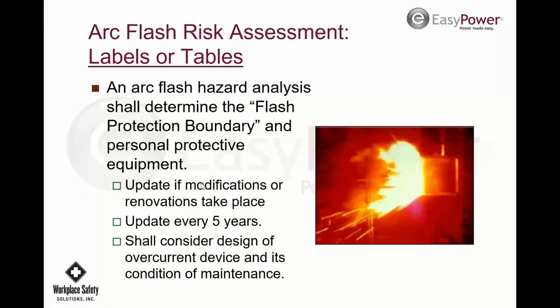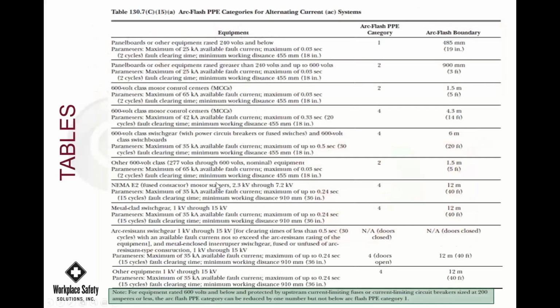Okay, we're going to talk about tables and labels. I want to go through this stuff if I can here. So this is the table that you would use. You look at what it is you're doing. So this is a 240 volt up to 600 volt panel, maximum of 25,000 amps, and 2 cycles of clearing time. If either one of those is not true, if you're not within the 25,000 amps, or you have greater than 2 cycles, then you can't use this. Those are the limitations of the tables.